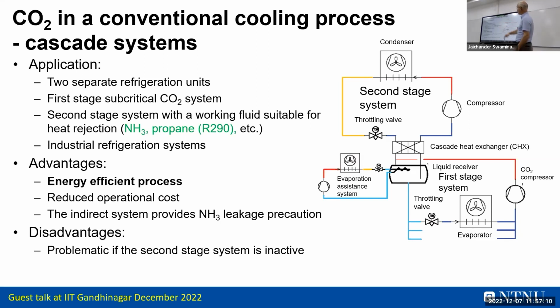It's very energy efficient. The challenge is that if this one fails, then this one cannot work, that's the problem. And if this is ammonia and here is CO2, you should not at all have a leak inside this heat exchanger, because then you get this powder, and the whole system is kind of destroyed because ammonia and CO2 react.